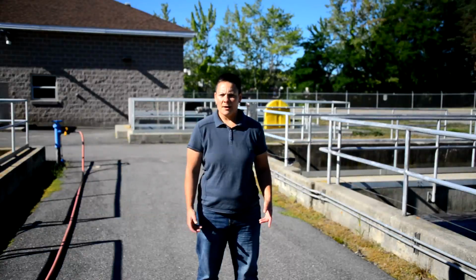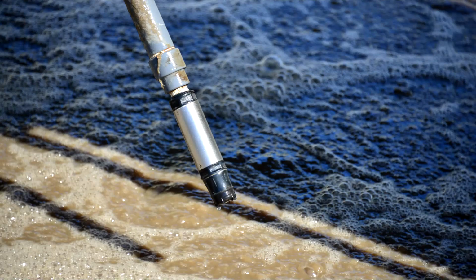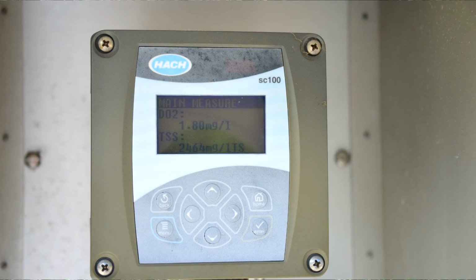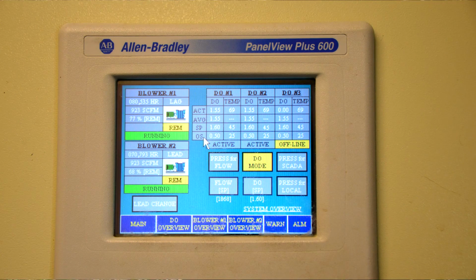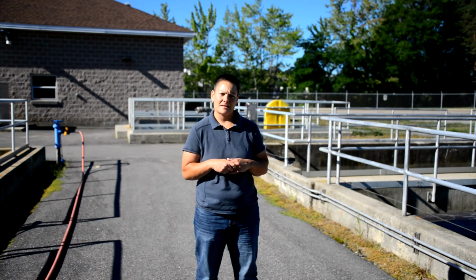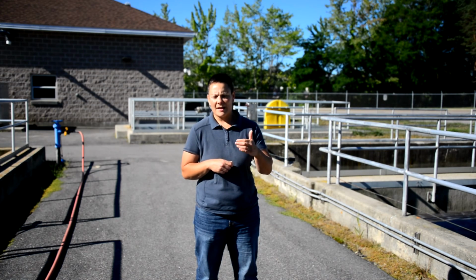At the city of Saco, we maintain our DO at approximately 1.5 milligrams per liter. Each aeration tank has their own DO sensor, which relays back to a PLC what that value is. Within that PLC, there are control loops that actuate valves on each of the head of the aeration tanks that modulate so that it can maintain that DO.